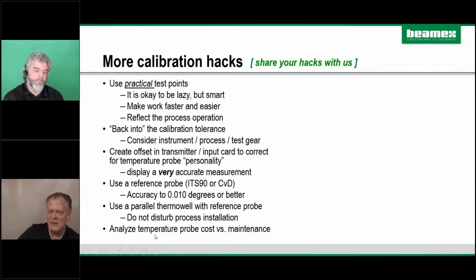And finally, you can always throw a probe away. I know a lot of you out there, if you question whether the RTD or thermocouple is bad, just put in a new one, especially if they cost less than $100. But if you use this concept of trimming either the input card or the transmitter, you can get more life out of your probes and still get a very accurate measurement. Because even if you replace it, you need to check what the loop indication is, so you're going to do that work anyway. So you can learn how long your probes should really last for a given process, and maybe get some more mileage out of them and save some money by utilizing an offset.